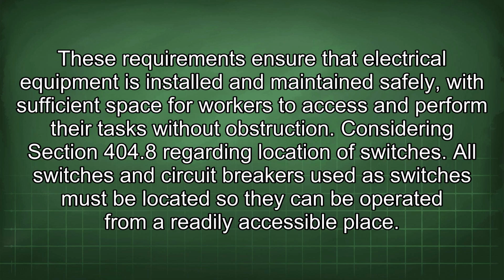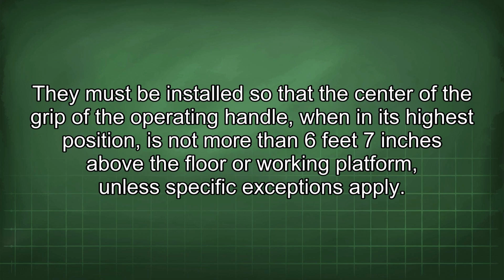Considering Section 404.8 regarding location of switches. All switches and circuit breakers used as switches must be located so they can be operated from a readily accessible place. They must be installed so that the center of the grip of the operating handle, when in its highest position, is not more than 6 feet 7 inches above the floor or working platform, unless specific exceptions apply.